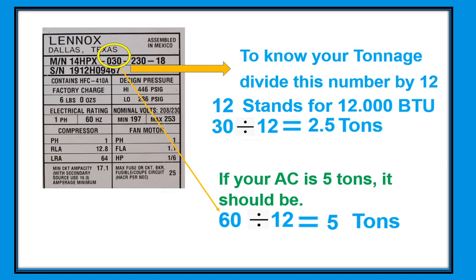Here we have an example using a Lennox air conditioner nameplate. To find the tonnage, divide the model number's key digits by 12, since 12 stands for 12,000 BTU. So 30 divided by 12 equals 2.5 tons — this nameplate is a 2.5-ton unit. If your AC is 5 tons, the number would be 60; 60 divided by 12 equals 5 tons.